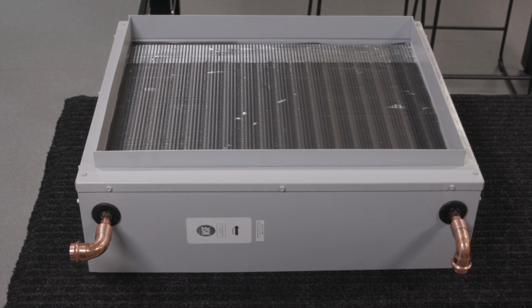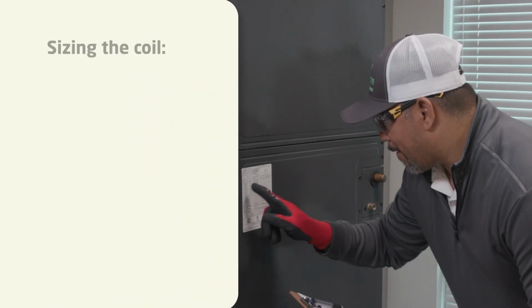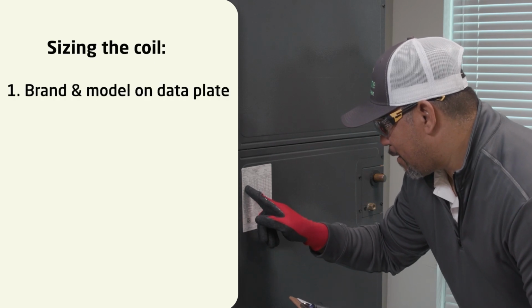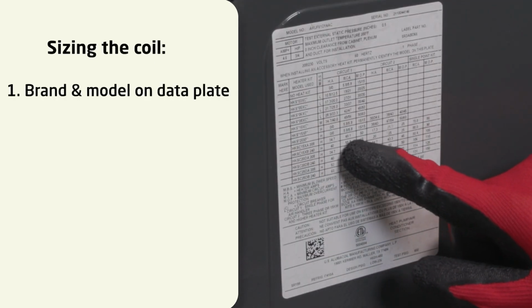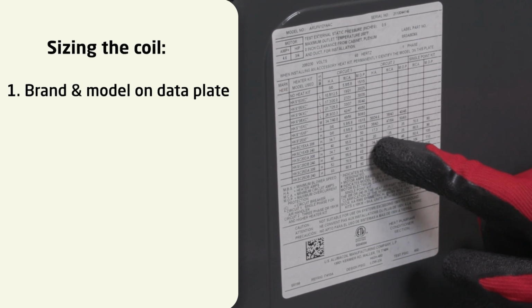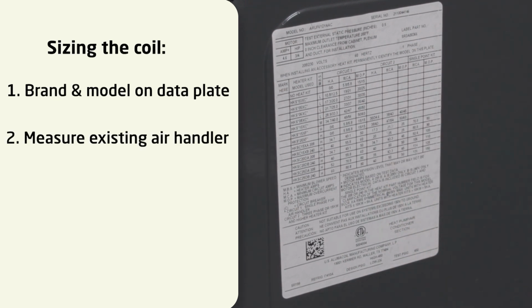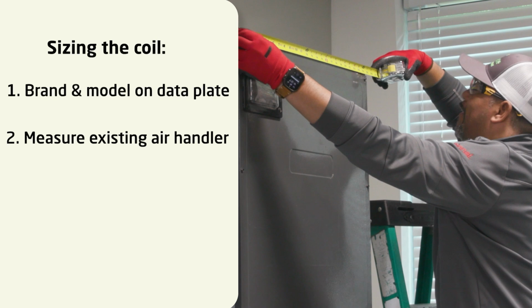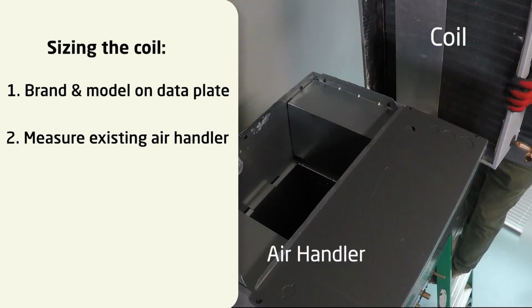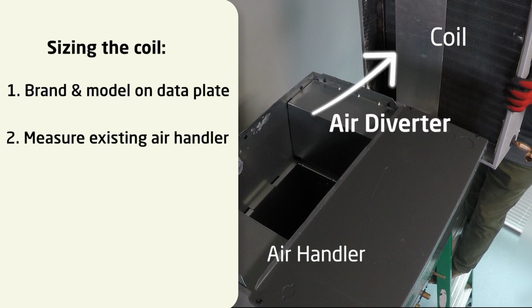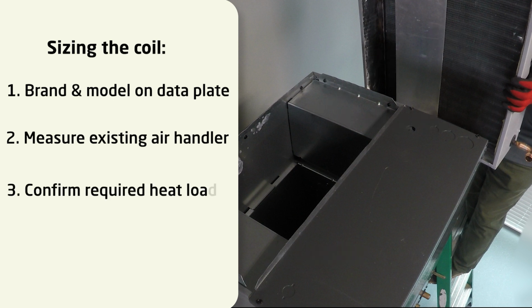Sizing the coil is very important. You need to check 3 things. First, get the brand and model number from the data plate on the side of the heat pump air handler. Second, measure the length and width of the existing air handler. Remember, your heat coil opening will be larger than the air handler. This is the reason for the air diverter located in the coil. Finally, you need to confirm the coil can handle the required heat load.